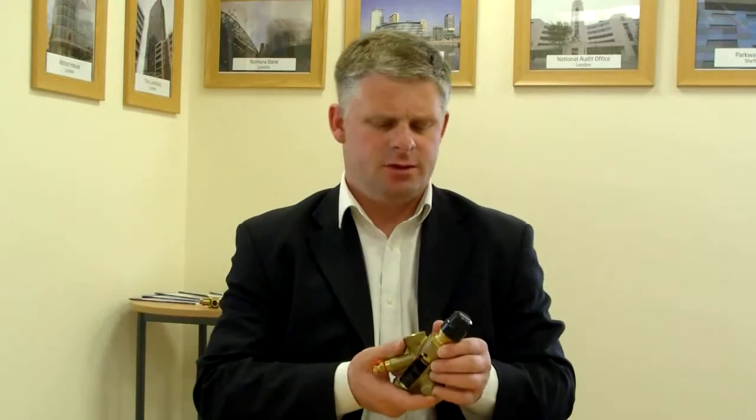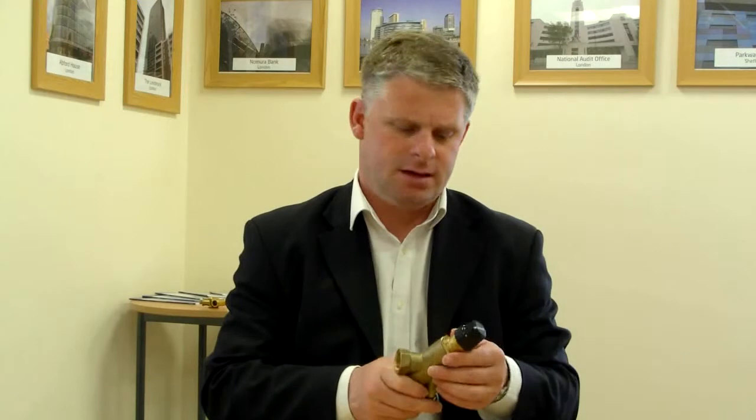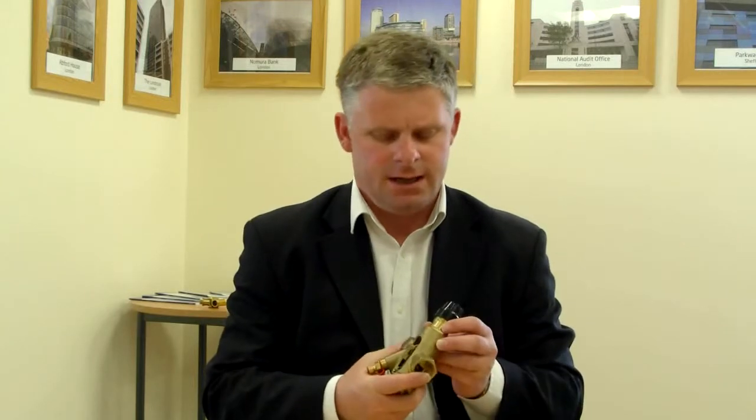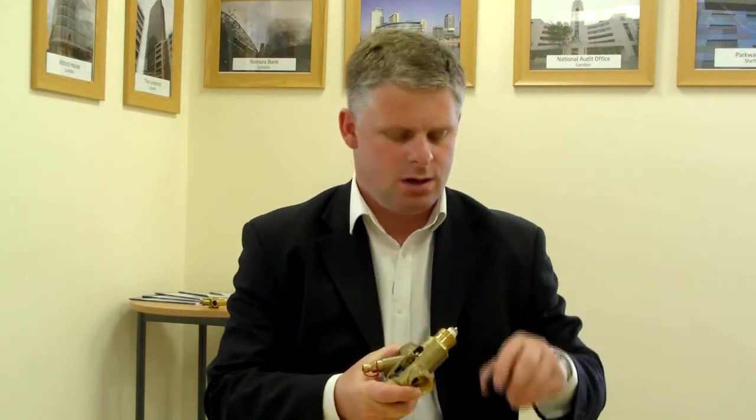Hi, this is a short film to introduce the Frese Optima Pressure-independent Balancing and Control Valve. This is a product made from brass de-zincification CW602N from a hot stamp forged process, and it is for installation on small heating and cooling coils for flows up to around 2.4 litres per second.